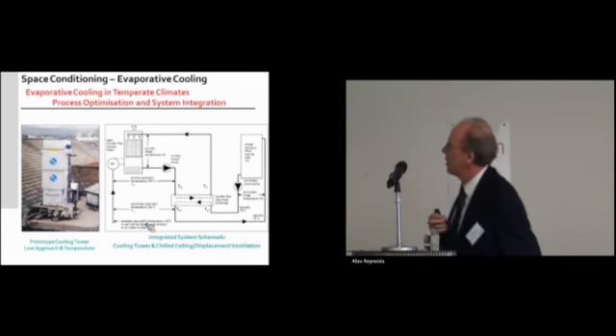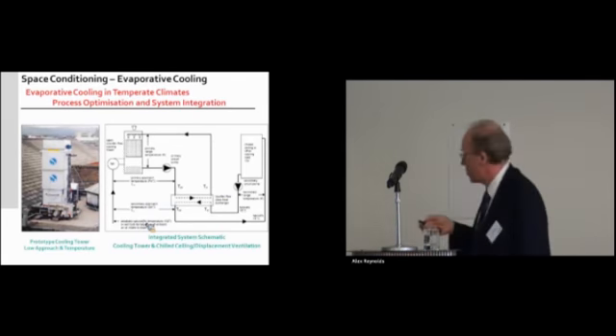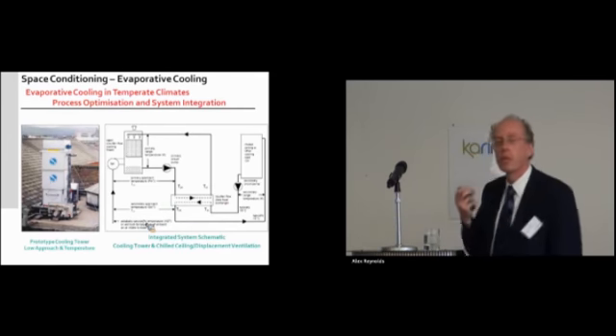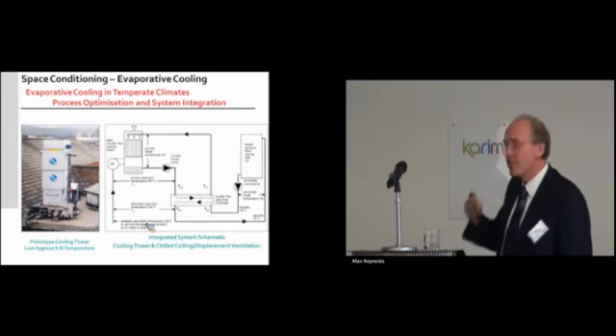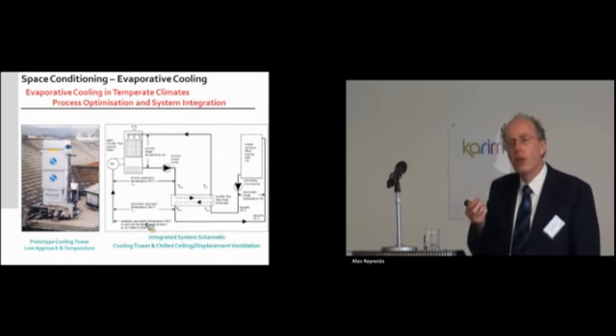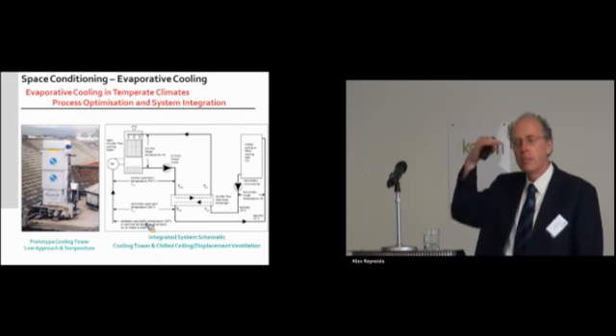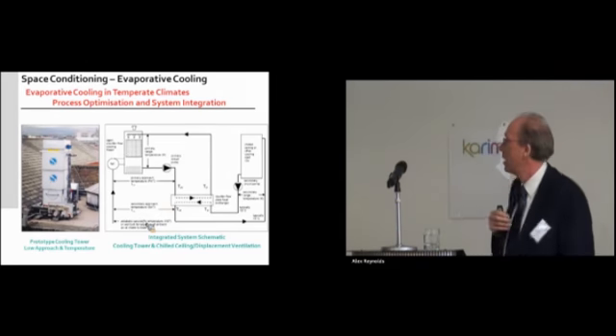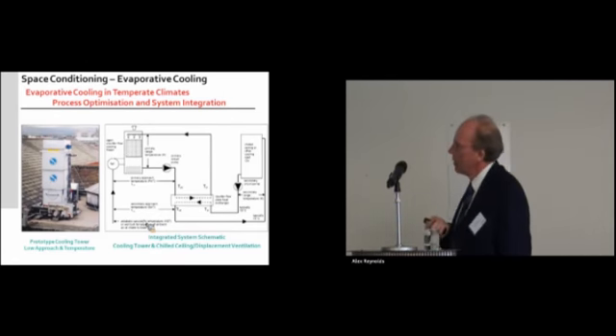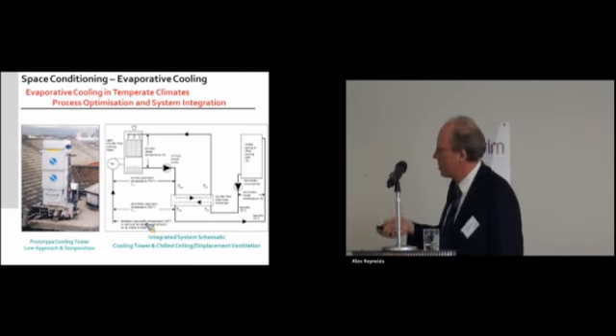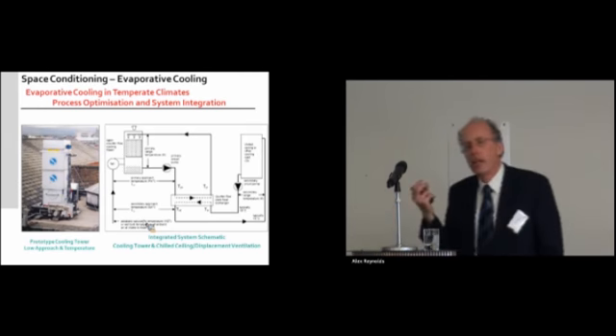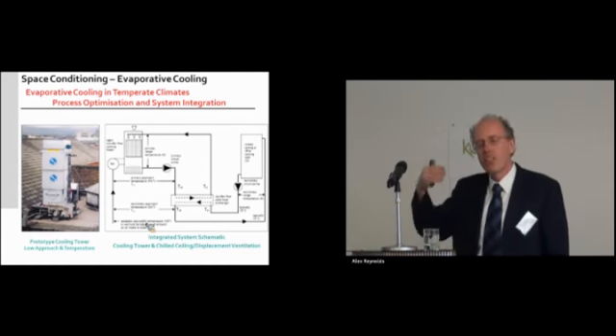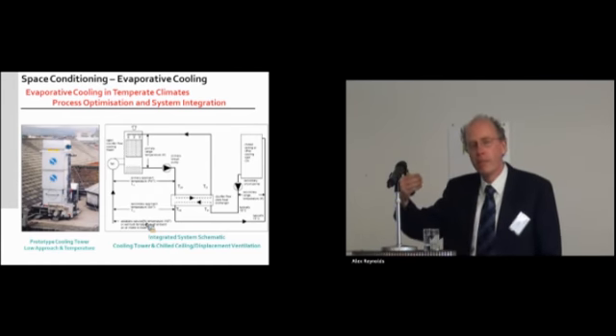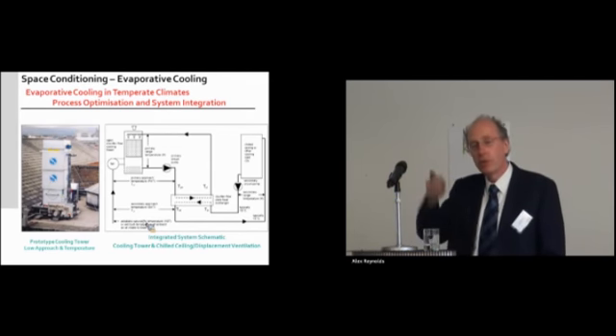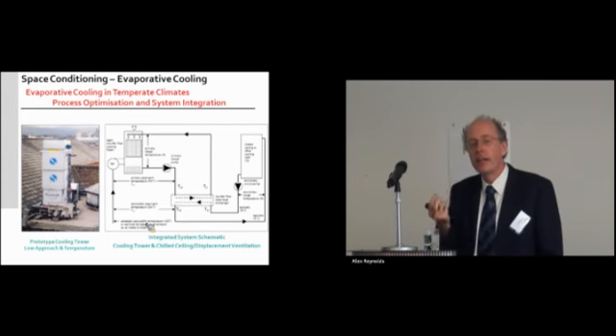Another piece of work which we've done is looking at evaporative cooling. This is where we use a cooling tower. This is a prototype cooling tower that we built. And this is used in conjunction with either displacement ventilation or with radiant cooling. That's chilled panels or chilled ceiling panels in buildings. And the hypothesis starting out with was that it was possible to design a cooling tower that could bring you to within less than 2 degrees of the wet bulb temperature, and to try and test this concept in the type of climates that we get in the UK and Ireland, essentially a mild temperate climate.